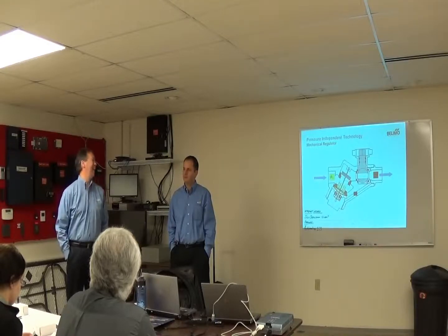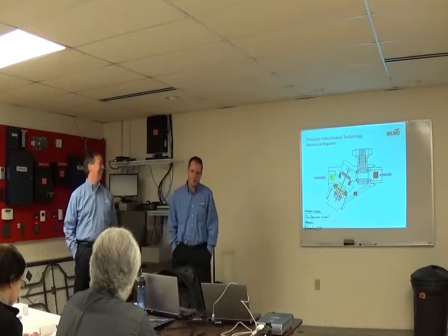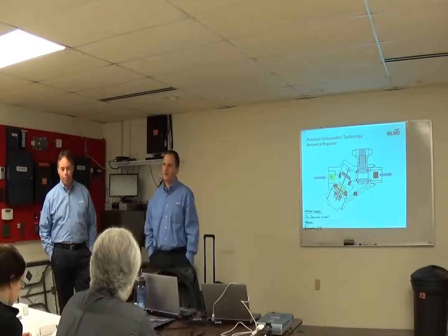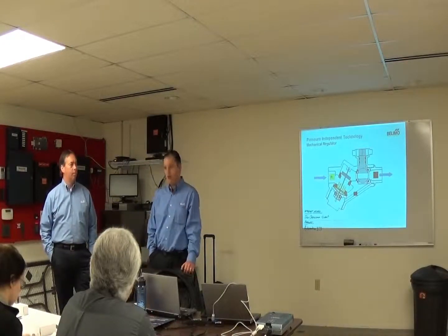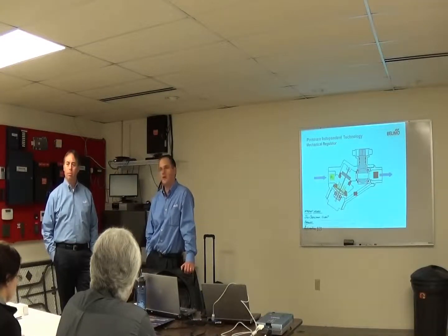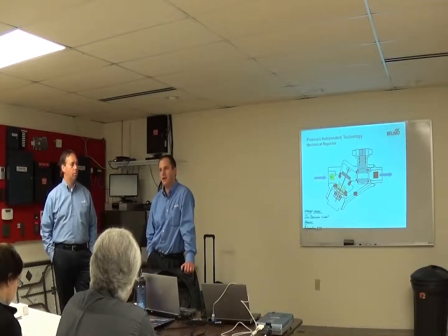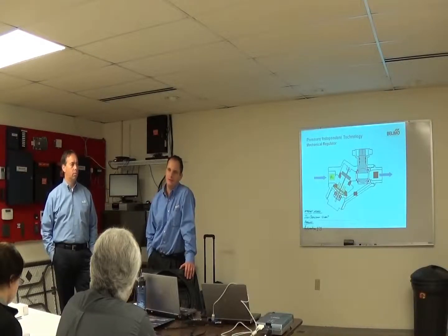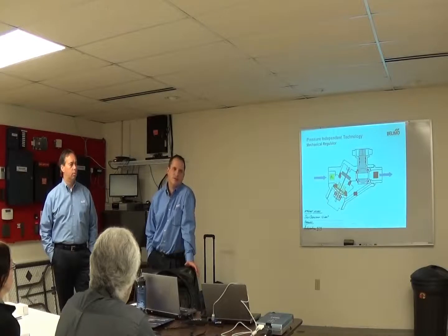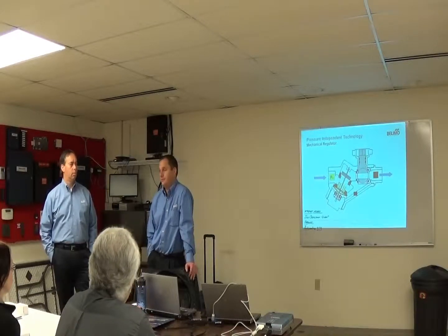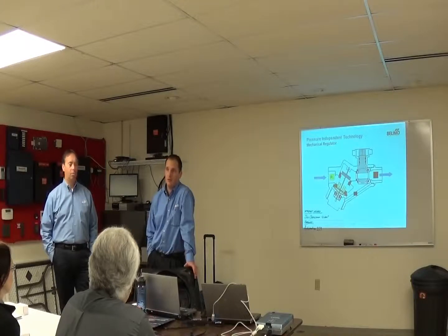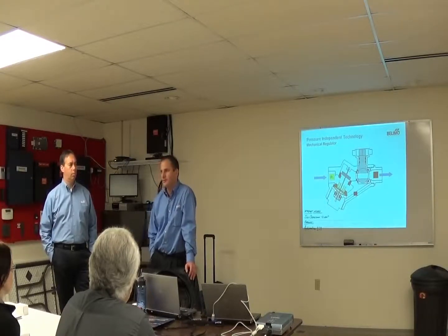Anything else to say about that? I'd say no, it's a sticking point. No recalibration is required at this point. I've looked at a lot of other manufacturers of flow meters, and for the most part, they're not really recommending recalibration either. So it's 2% accurate. We've had some pushback from, I don't know, a handful of people when they're doing metering and trying to bill somebody with 2% accuracy. I'm thinking, okay, 2% accuracy is still pretty good. You're not talking a lot of difference at 1,000 GPM, 2% accuracy was at 20 GPM or so.